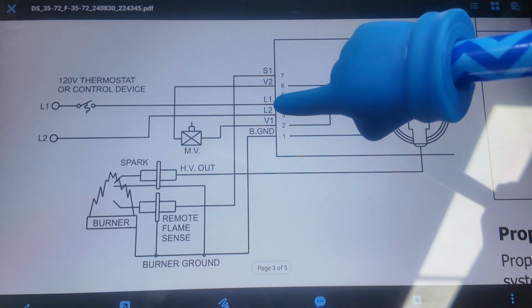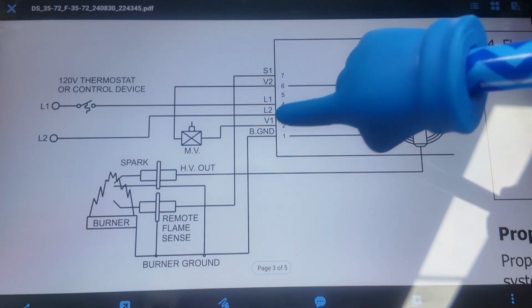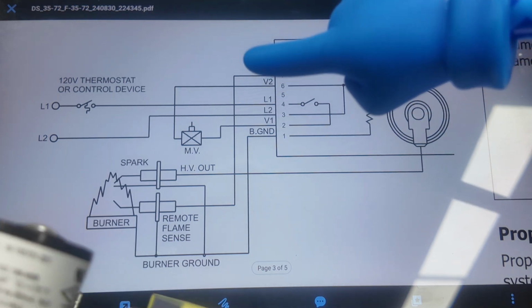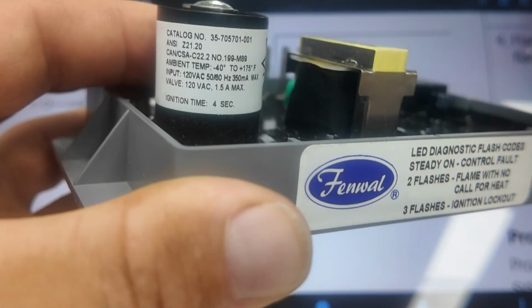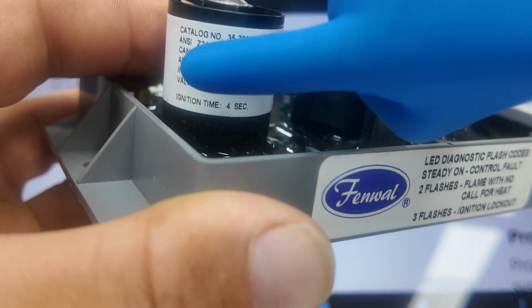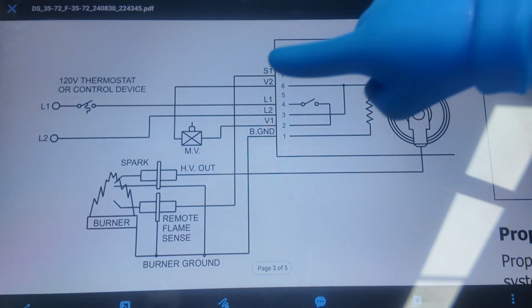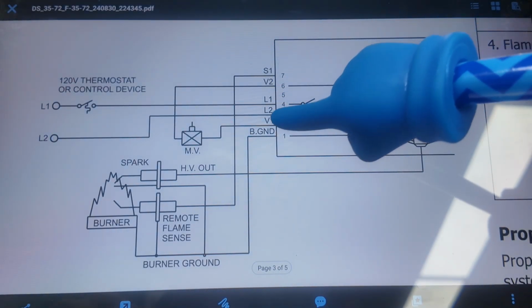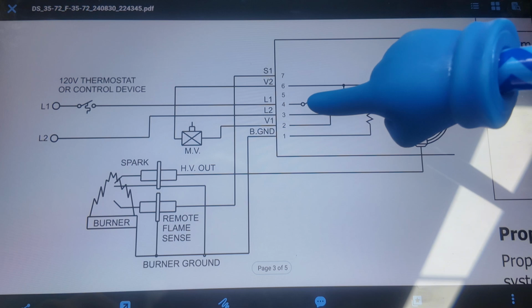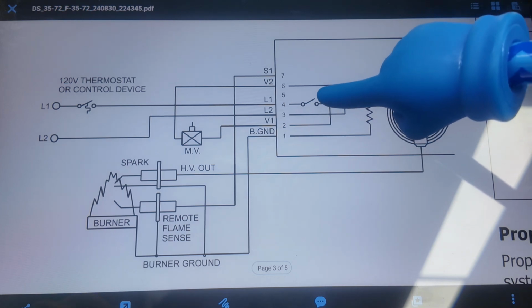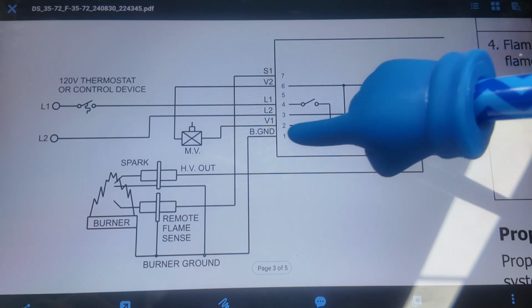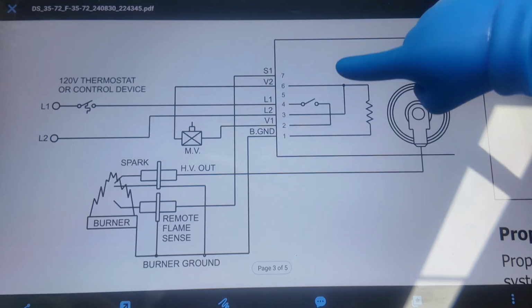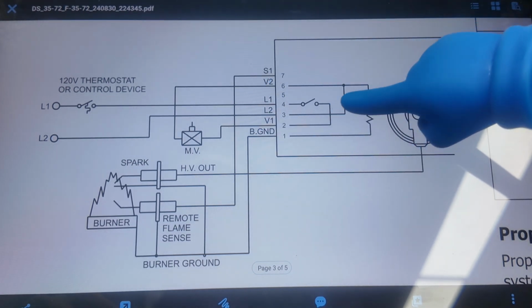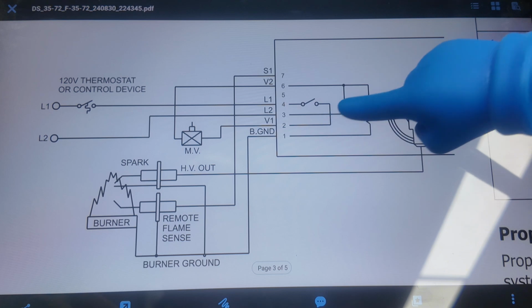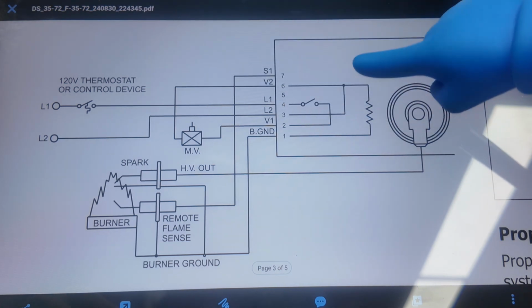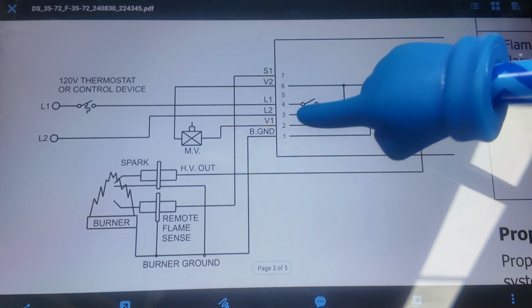You're going to have the ignition time. You put power there and nothing is going to happen for however long the ignition time is. So on here it's 4 seconds. So we put power to L1 and neutral to L2. And after 4 seconds, this switch closes and it puts electric out V1. So V2 is connected to L2. And that's all connected. We have this connected with a resistor.